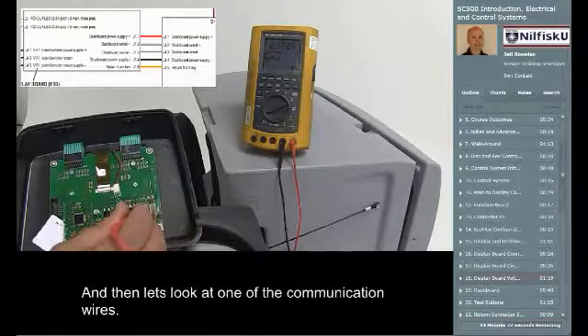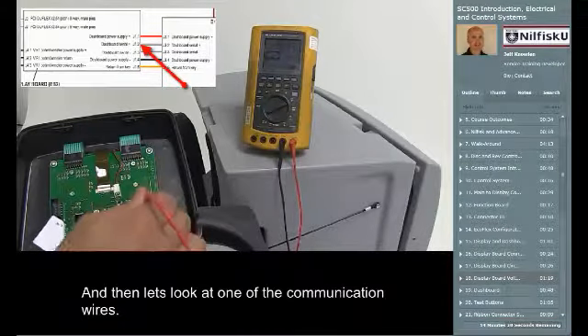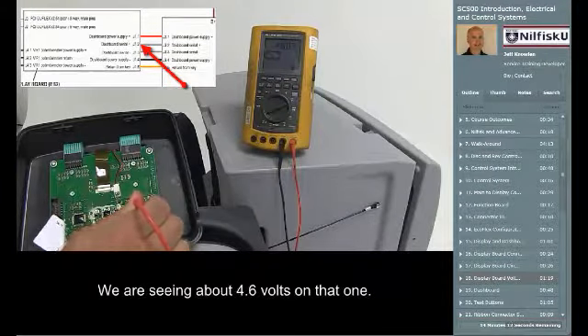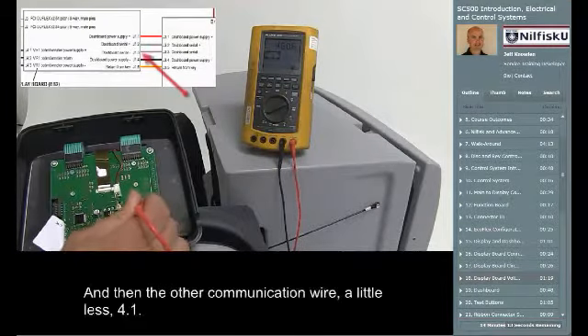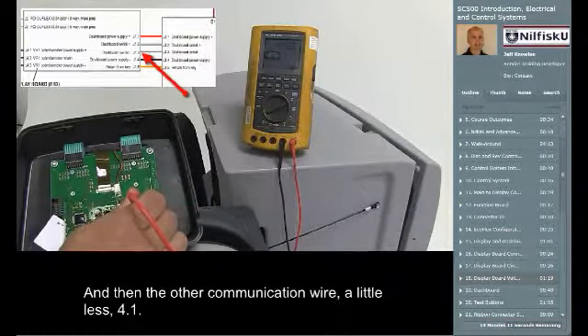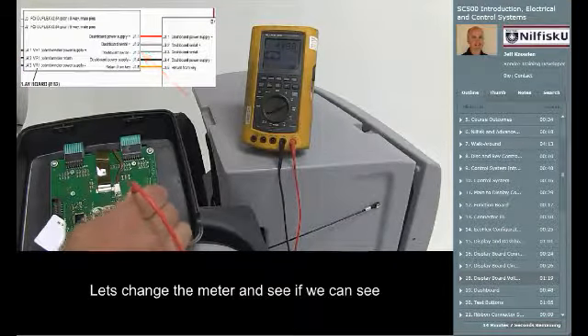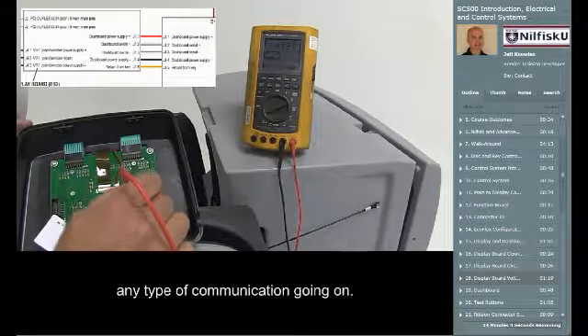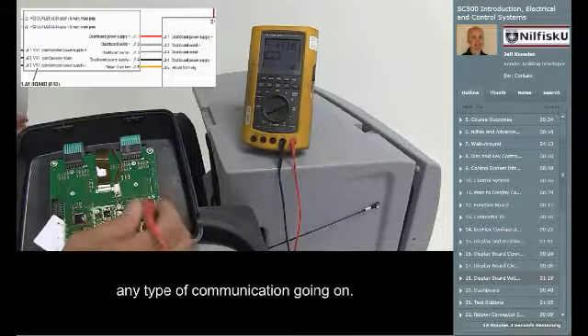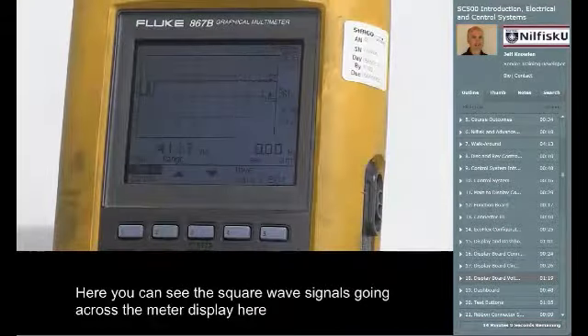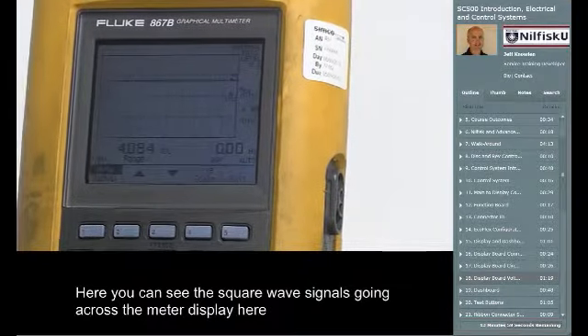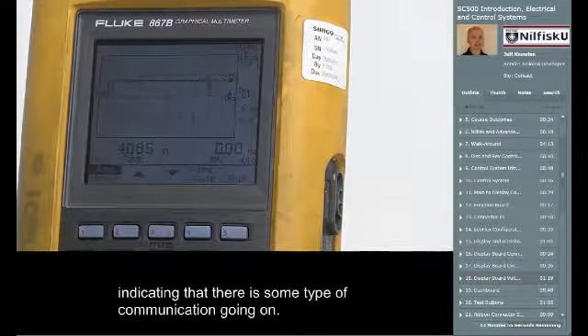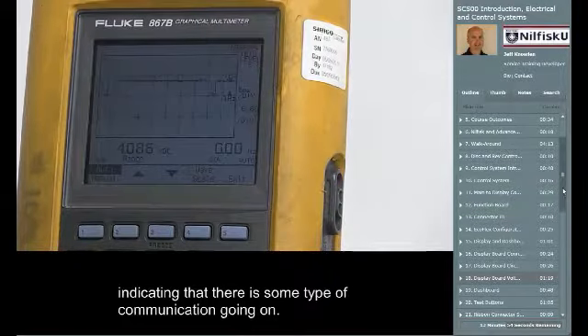And then let's look at a communication. One of the communication wires, we're seeing about 4.6 volts on that one. And then the other communication wire, a little less, 4.1. Let's change the meter and see if we can see any type of communication going on. Here you can see the square wave signals going across the meter display here, indicating that there is some type of communication going on.